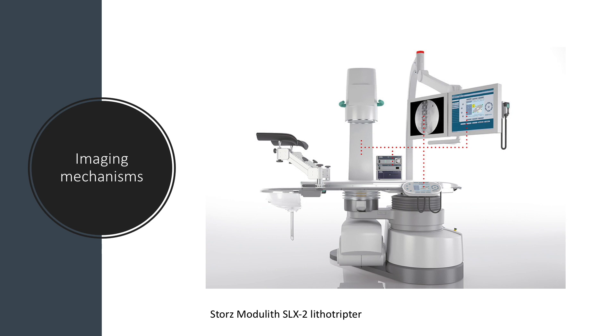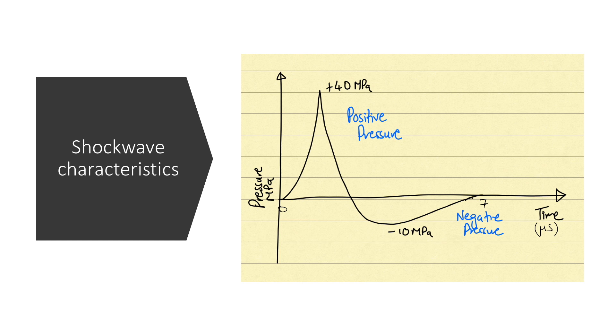Regarding the imaging modality, most modern lithotriptors have both fluoroscopy and ultrasound to enable localisation of even radiolucent stones. Those are the components of the lithotriptor. Now let's think about the actual shockwave. Here you can see a shockwave illustrated, with pressure on the y-axis plotted against time in microseconds on the x-axis — the pressure being measured at the focal point of the lithotriptor, i.e. the stone.